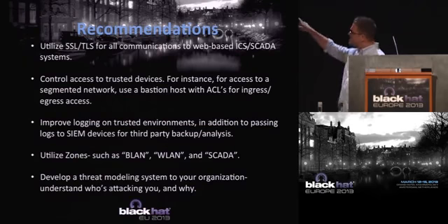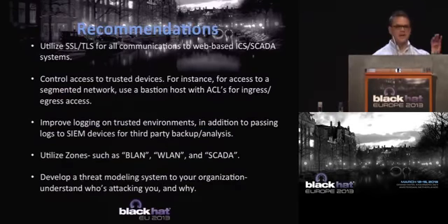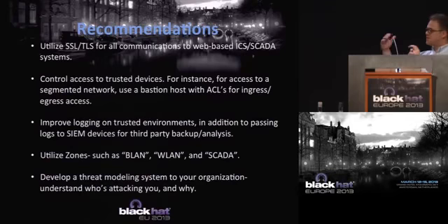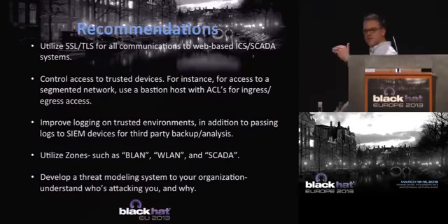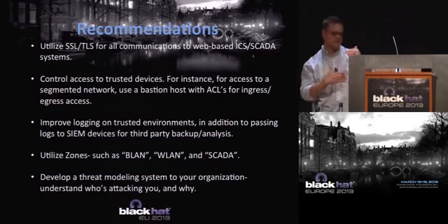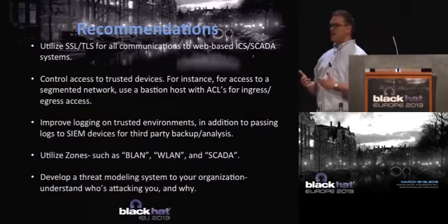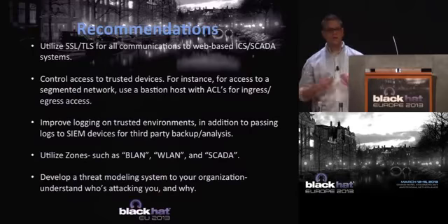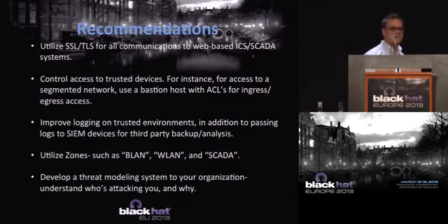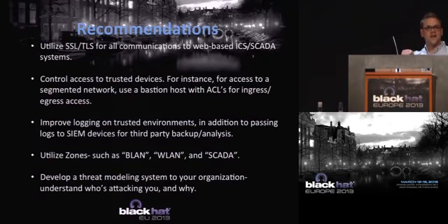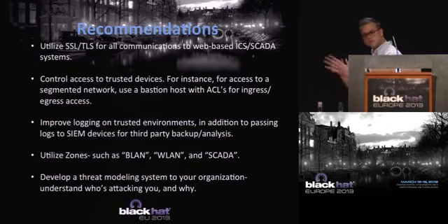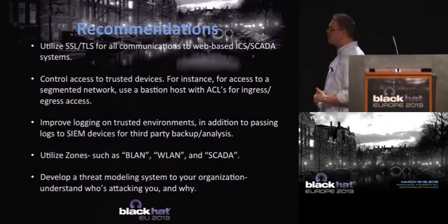So use a Bastion host with ACLs, and whenever I say a Bastion host, I'm referring to a central server that is actually in between two different WAN segments. So between a SCADA WAN segment and a PLC segment, put a Bastion host, and that's the only host that can gain access into that network. That is used with great success, and for those of you that are tasked with trying to improve security very quickly, a quick win is deploying a Bastion host concept and saying, only that host can access only those devices. So utilize that concept. It's very quick and it's a good win.